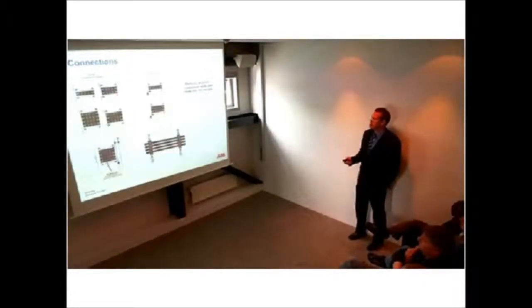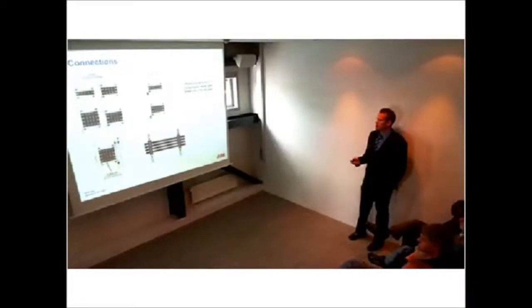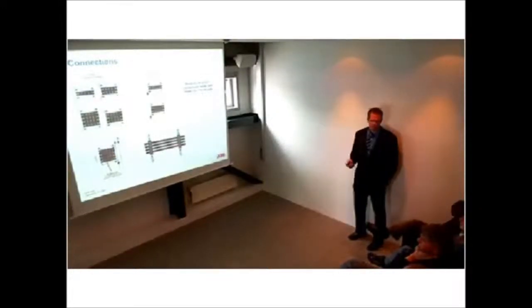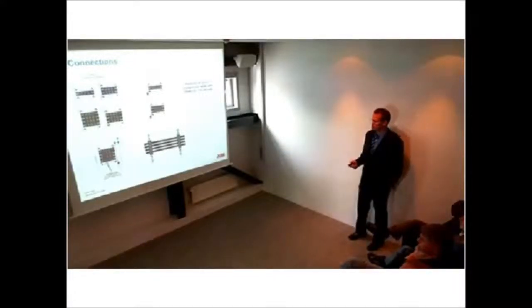low voltage connection we have now, because we usually don't deliver these cable clamps for the low voltage. So this is short circuit proof tested at our short circuit laboratory in Skien, 50 kiloamps and 100 kA peak. This is tested because we're going to test the strength of these clamps. So you can have 1 parallel cable, 2, 3, and 4 parallel. So what we tested in our short circuit laboratory was this with 4 out of 16 cables, 240 square millimeters.